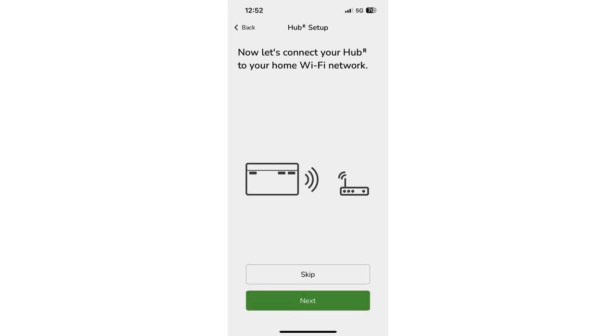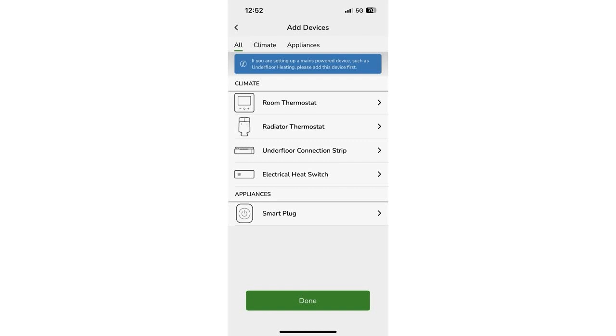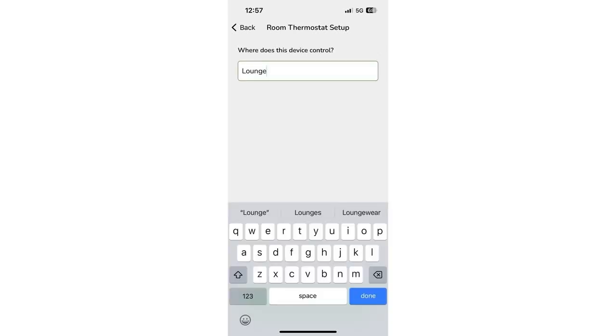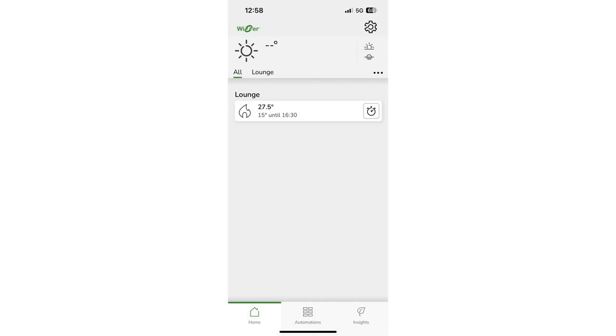There's an option to set up the home Wi-Fi during installer setup, though I normally steer installers away from this — it's the customer's domain. However, if a hub has been sitting on a shelf for six months the firmware may be outdated, and newer devices like Wiser underfloor heating or the electrical heat switch may not appear as options until connected to Wi-Fi and updated. Once all devices are added and assigned to rooms — up to 16 virtual zones — you have the same control screen the customer will have, but your phone is talking directly to the hub.